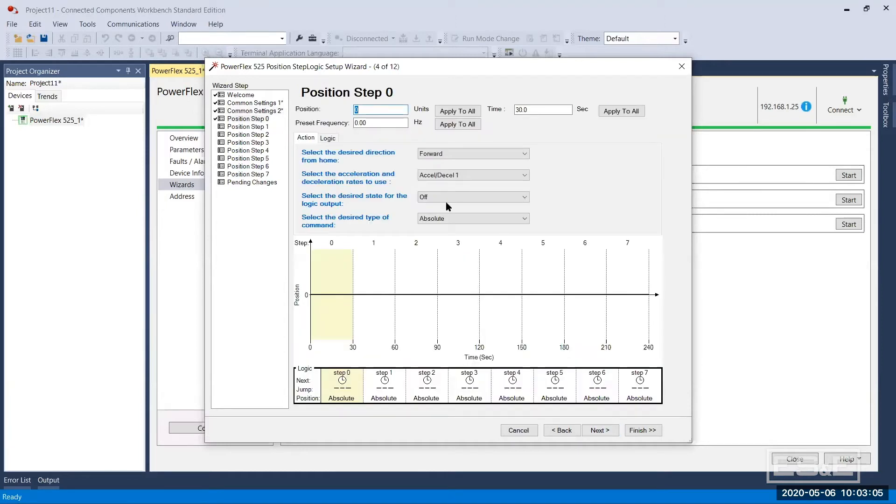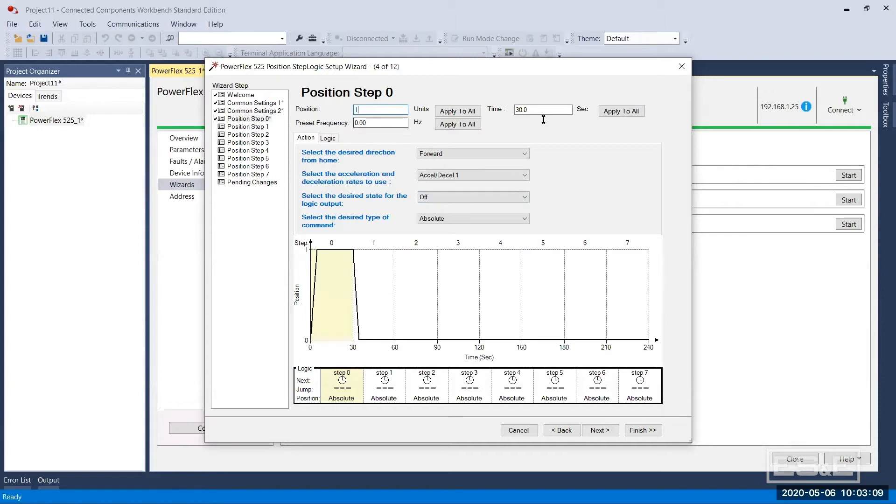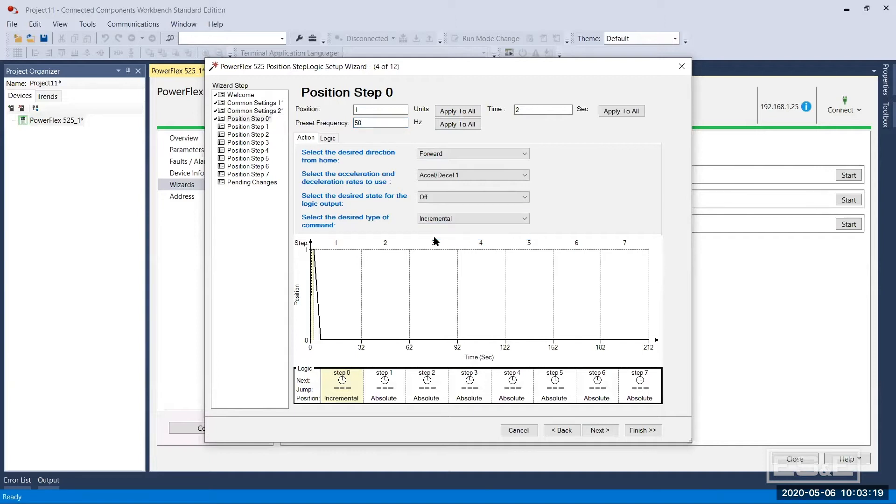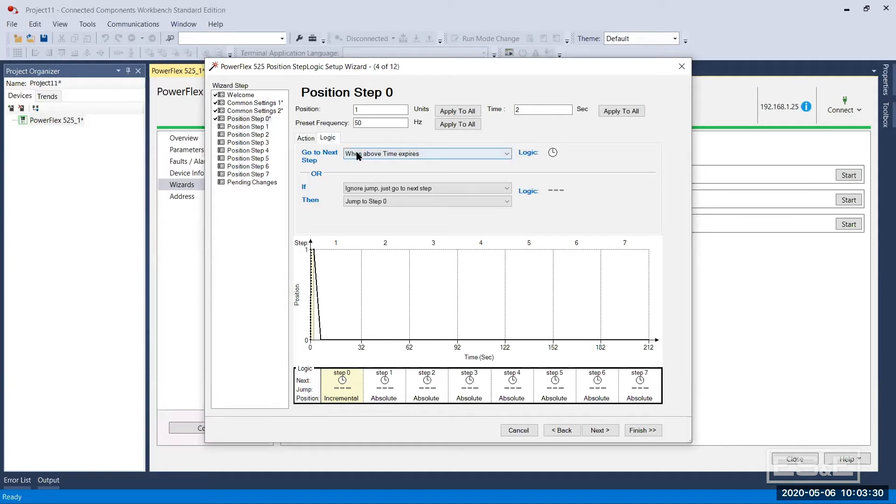So now I'm going to say my first position, position step zero, I want to make one revolution and I'm going to give it two seconds and let's do it at 50 hertz. Now it may not reach 50 hertz because my accel is a half a second. I'm going to make it incremental, which means it's going to increment from where it is right now because I'm not homed and I don't have an absolute home at this point. I'm just going to start from where I am and it's going to go to my next step when my time expires.